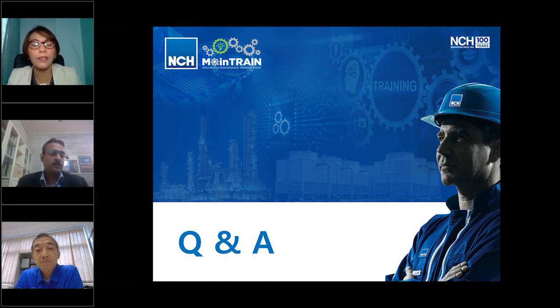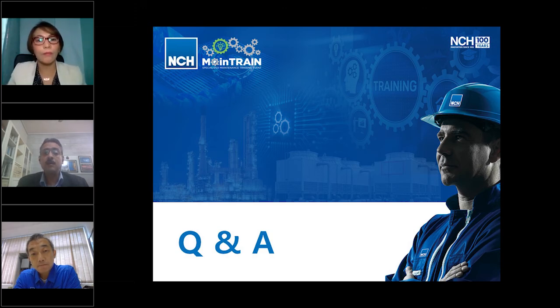You need additional design to remove or balance the impurities inside the system. Once we stop the blowdown, all the salts remain behind. What do they do? They create more scaling or corrosive tendencies. So you need good chemical treatment, very strong chemicals that can control very high LSI and very high cycles. Are they available? Yes, you can talk to one of our consultants, and you'll be shocked at the kind of limits we can achieve.